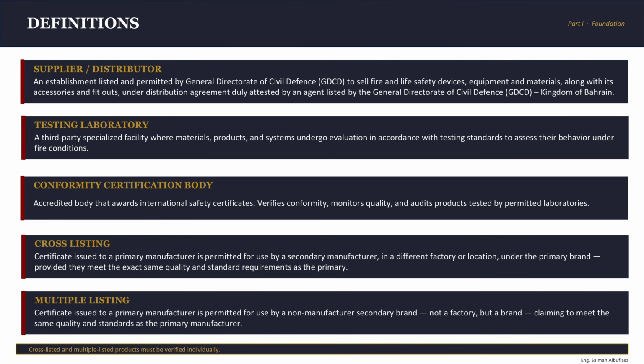Let's take another example in order to simplify it. Let's say Navco, a manufacturer based in Dubai, one of the largest fire protection manufacturers in the region. Their fire pumps carry UL and FM listing and approval marks. Both verified, both active, both earned through full testing, factory audits and surveillance. Now, Navco opens a manufacturing facility in Bahrain. Same company, same brand, but different factory, different location. They cannot assume that the Dubai UL listing automatically transfers. No. UL sends quality auditors to Bahrain. They verify the manufacturing process, raw materials, quality controls, and production consistency. And then UL confirms that the Bahrain output is identical in fire performance to the Dubai certified product. Only then is the Bahrain facility cross-listed under the same certification.